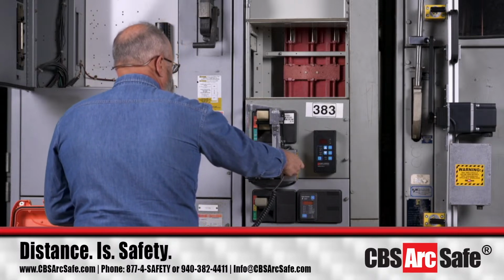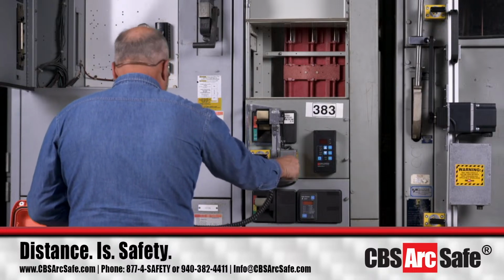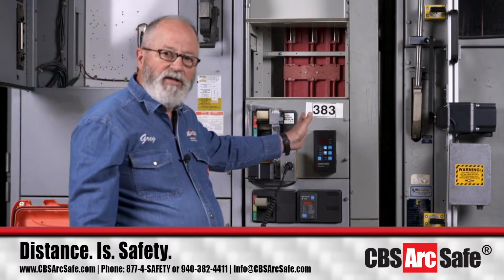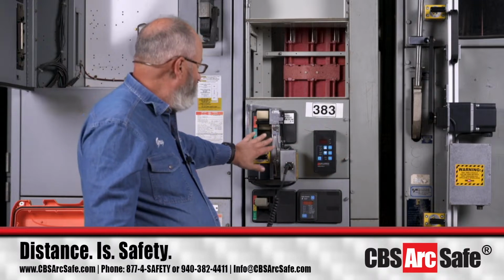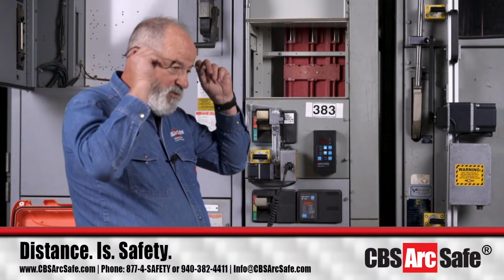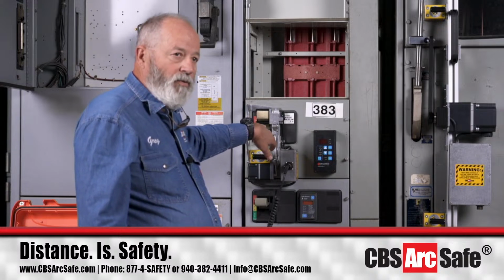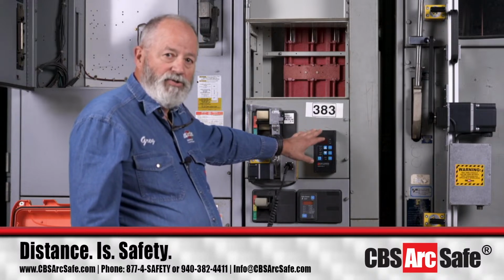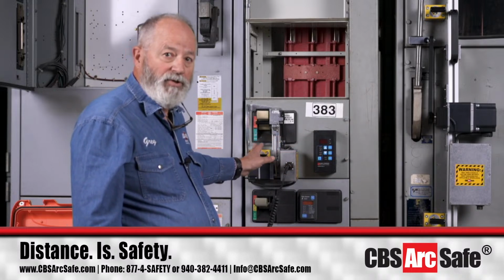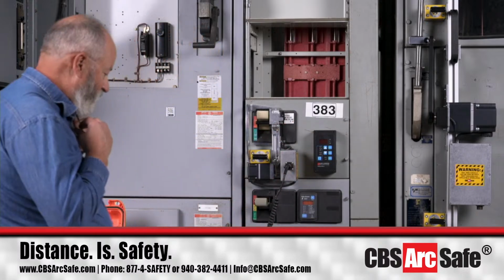Both motor starter actuators, whether you're using the RSK or the RSA, are made to operate. Just to explain something, sometimes you can have a double set of handles on an MCC bucket, and either this one or the other one, the RSK, will be able to accommodate that. Sometimes if you've got a lockout tagout on the left handle and you're trying to use the RSK, you may have to remove the lockout tagout to be able to use the RSK, because it can interfere with the mounting process and how it would actually set up. So just be advised of that.